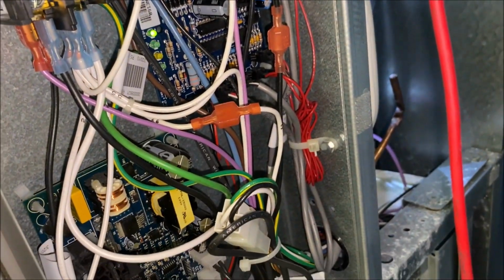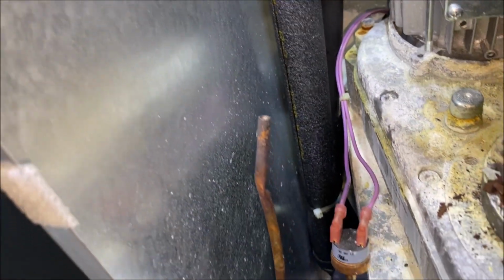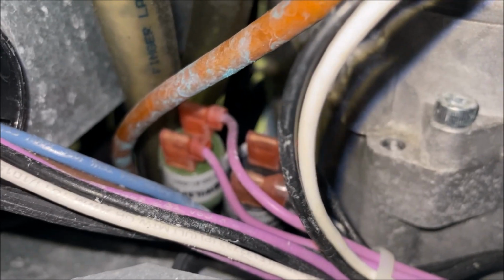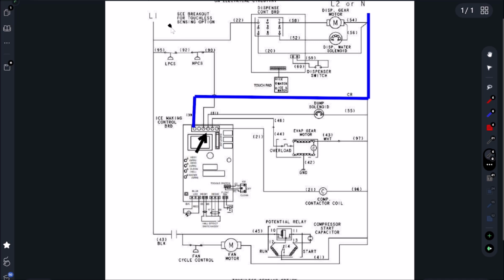All right, so I do have 120 volts again at my board on this wire number 90. So that means one of the switches has closed its contacts. So it's either this low pressure switch right here, this high pressure switch here, the 2 purple wires, or that fan cycle control is not working. So there's 4 components in question: low pressure cutout, high pressure cutout, fan cycle control, or the fan condenser motor. Okay, every time I go to test these components, I'm gonna have a 15-minute delay. So if I go test this low pressure control switch and the switch opens up, I'm gonna have a 15-minute delay.